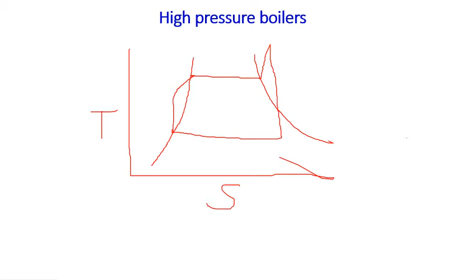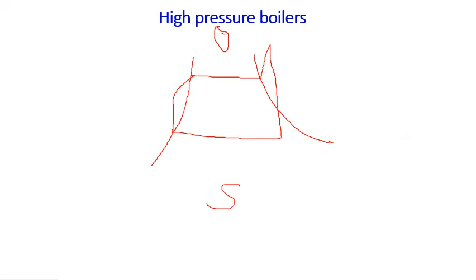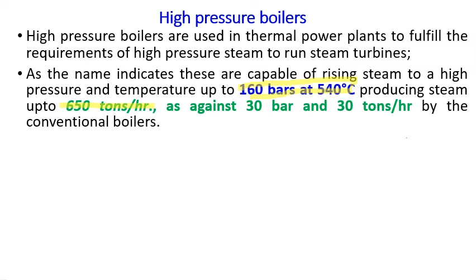And if you remember this, at the topmost portion we have the critical point, and the critical point is around 221 bar. So the medium pressure boilers are working at around 75 bar, those are conventional boilers. But the high pressure boilers are working at more than 75 bar, surely less than the critical pressure of 221 bar. The high pressure boilers are used in the thermal power plant to fulfill the requirement of high pressure steam. As the name indicates, here it is 160 bar, right? We have discussed that point in the earlier slide, and it is up to 650 ton per hour. Large mega power plants like UPCL and Raichur power plants are working with these kinds of boilers.